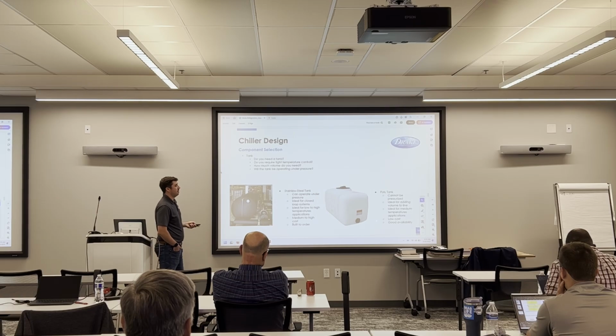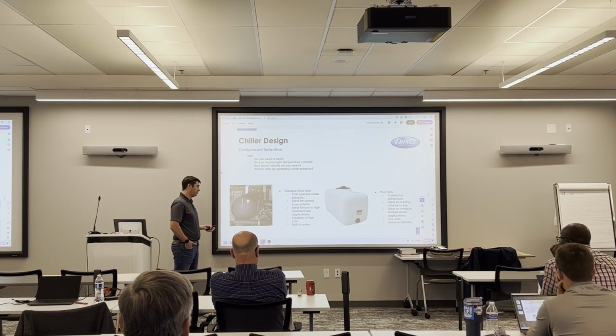And then the other option here is a poly tank. So it's a plastic tank. You can't pressurize a plastic tank, so that's one of the downsides. It's good for adding volume to your system for sure, but being that it's a plastic tank, I don't recommend using it for anything other than medium temperatures, which I would say is 50 to 70 degrees or so. If the fluid gets too cold, the tank becomes brittle, it can fail. If the fluid gets too hot, the tank gets warped, it can fail. It's low cost and good availability. You can buy them on Amazon if you want to.